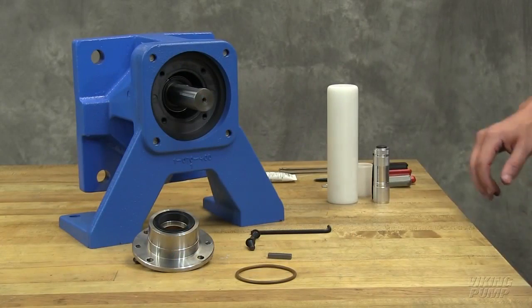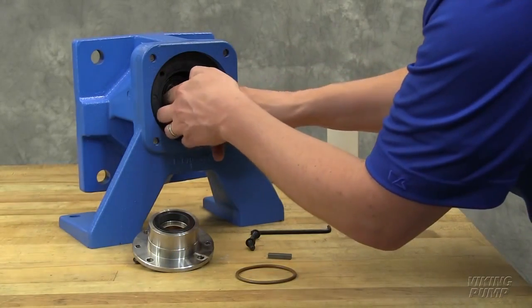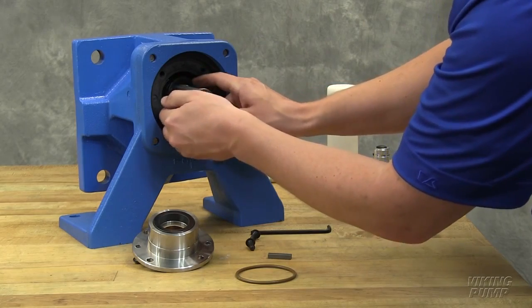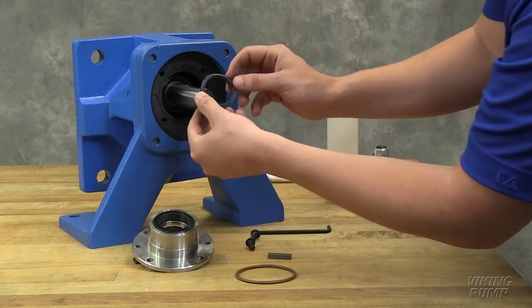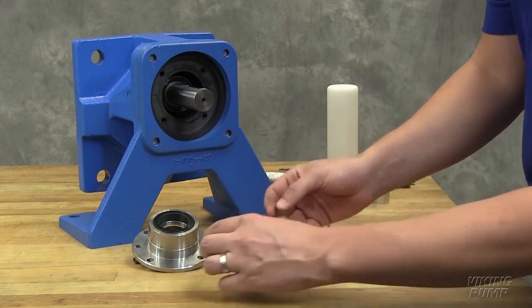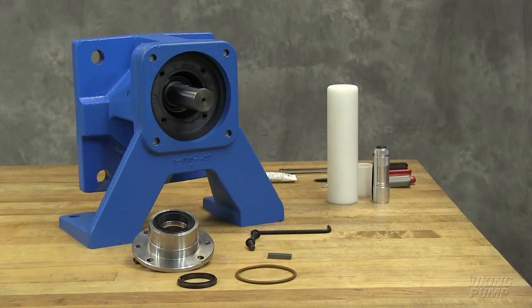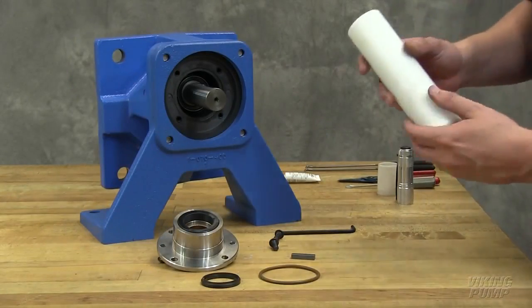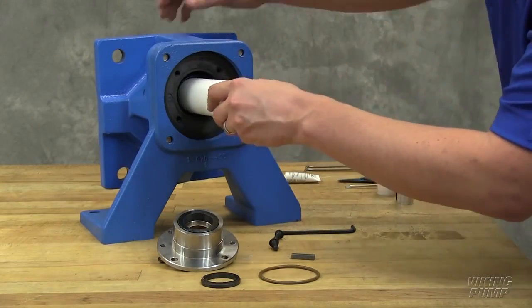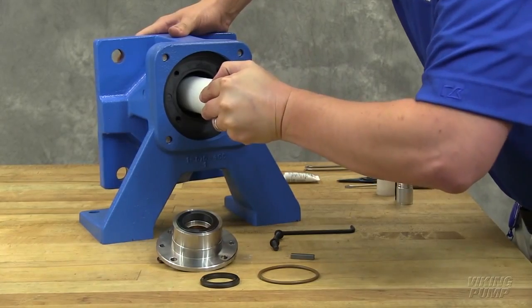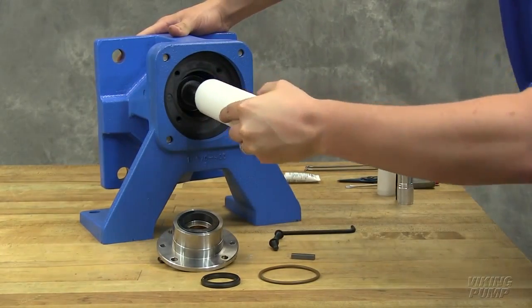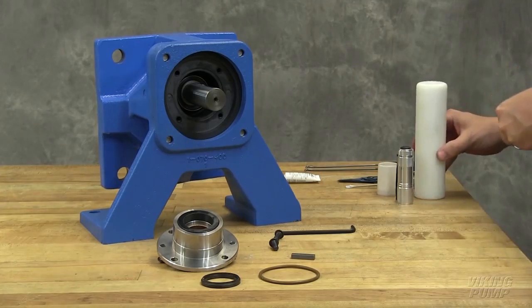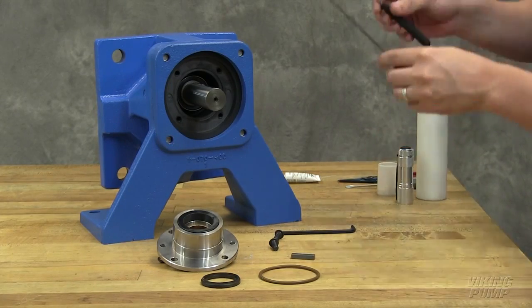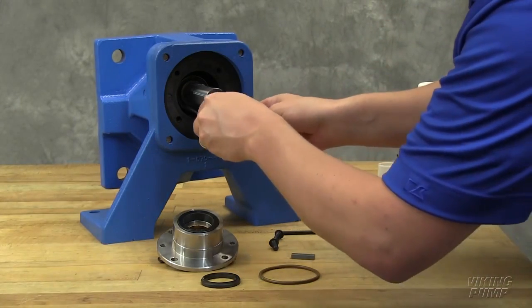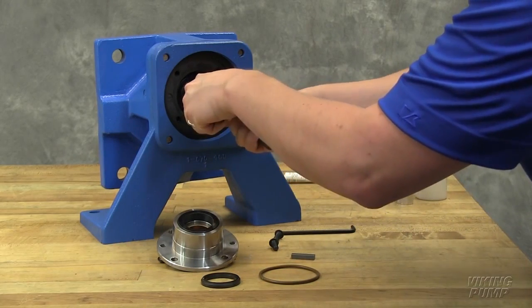The mechanical seal is made up of 2 primary components or parts. The part closest to the shaft end of the pump is the stationary seat. The part furthest is the rotating part. Remove the carbon element from the rotating part if it's still attached. Then use a pair of picks to reach into the seal chamber to hook the seal spring and pull the mechanical seal out. This is a bellows type of seal, and the bellows is designed to grip the shaft to drive the rotating part. It may take some effort to pull the seal out.